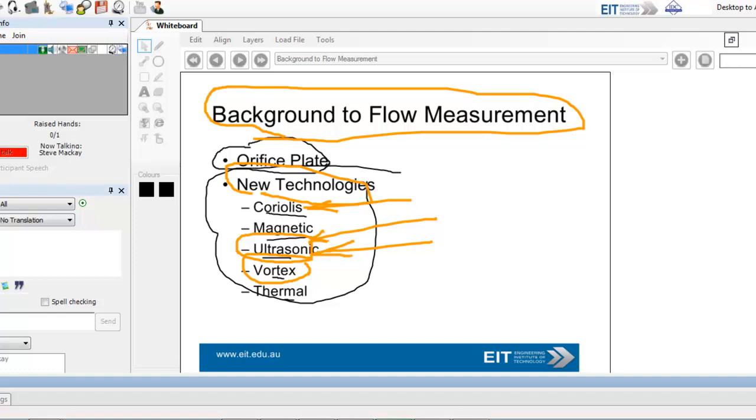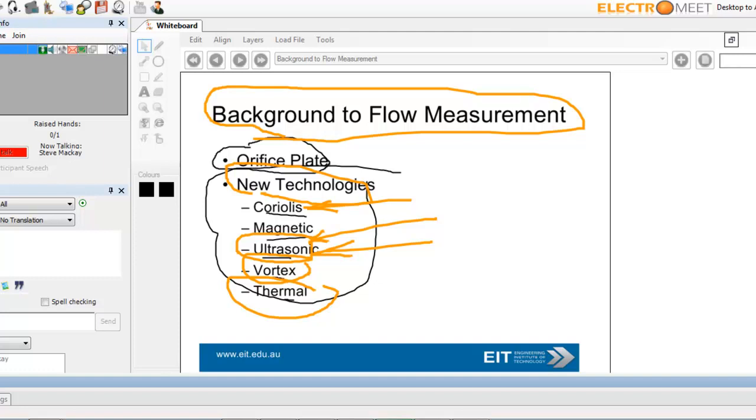Last one is thermal, which is probably not of much interest to anyone here, but I'll just quickly talk about it. Thermal developed in the 60s. I did a bit of work with thermal flow meters with medical applications, and there, what you're doing is you're looking at heat into the flow stream, and basically what you're trying to look at is when you're heating up an element in the flow stream, how much heat dissipates. So from that heat dissipation, you can then work out the flow rate. Obviously, the higher the flow rate, the more the heat dissipation. So there's two types of methods, constant temperature, and the other one is constant current method. Advantages are, you can handle large line sizes, it's very good at gas flow, and it's reasonably priced. Disadvantages are limited accuracy, and of course you've got to specify the gas being measured, and you can't use with liquids as easily, and certainly not for steam.